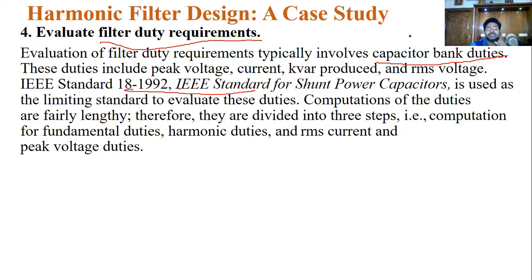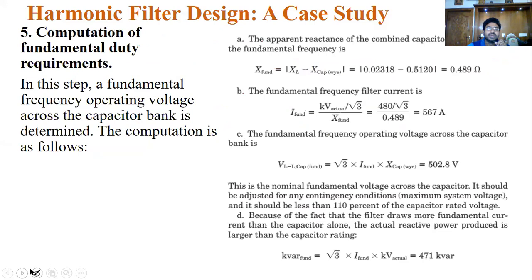That is defined by, or you can follow, the IEEE standard number 18-1992, a standard for shunt power capacitors. You can follow those standards. What is the fundamental frequency here? What are the harmonic duties? What is the RMS current? What is the peak value of that current? You know that very well. So you can take those values. They have given some tables and you can follow them.